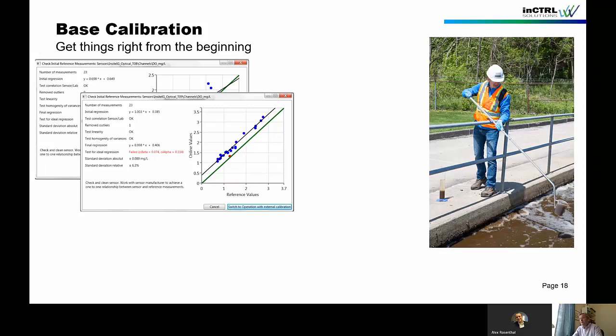Same case here, but you see that all the blue dots are actually on the black line, which is the new calibration curve we calculated in our monitoring and control platform. This is a screenshot from there. It's clear there is a bias in that measurement, and we were able to put that bias into the sensor. So we recalibrated the probe, and then everything was fine.